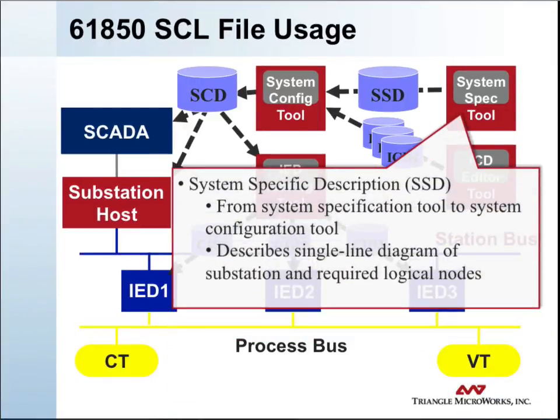The system-specific description files, or SSD files, are typically created by a system specification tool, and it's used to describe the overall substation specification to the system configuration tool. Basically, this is the description of the single line diagram of the substation and the required logical nodes to implement the functionality needed.